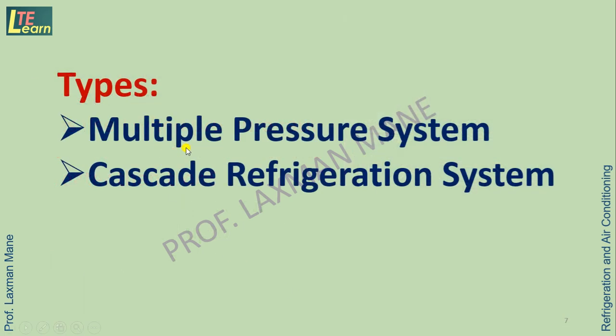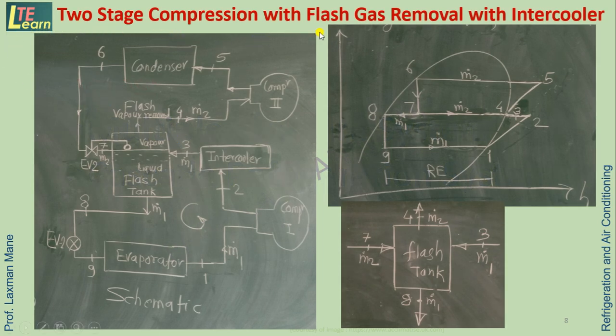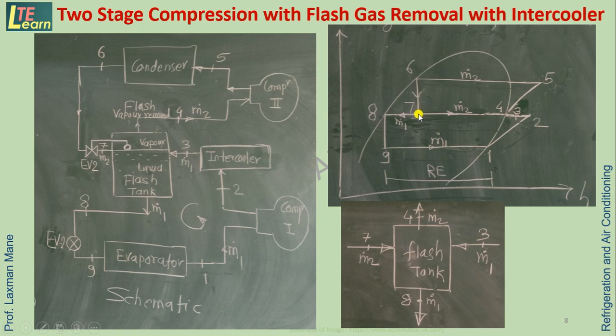Types of multiple pressure systems include the multiple pressure system and the cascade refrigeration system. Taking the example of a multiple pressure system, here is a two-stage compression system with flash gas removal and intercooler. Between the two compressors, intercooling is needed, so an intercooler is added. When the first expansion takes place and second expansion takes place, flash vapor is removed before the second expansion using a flash tank.